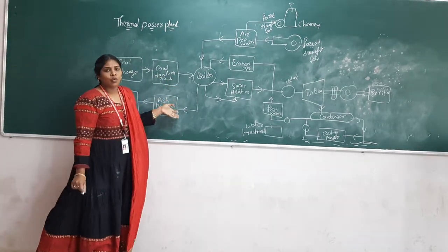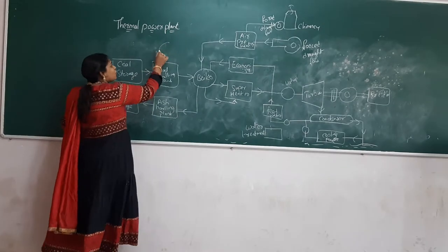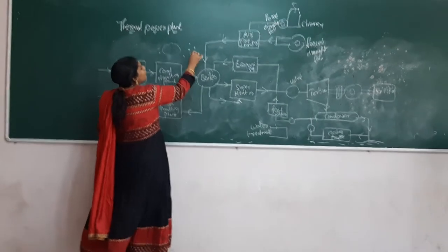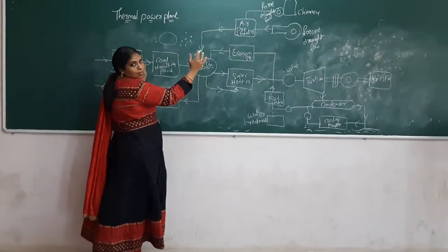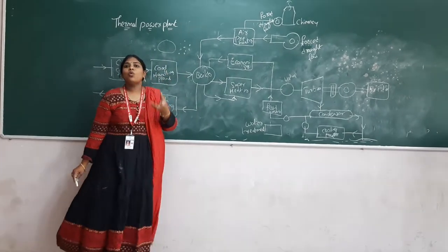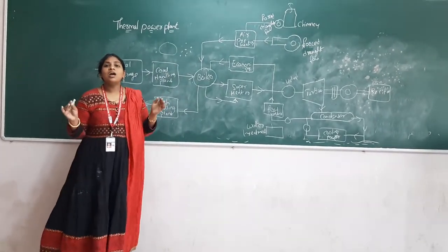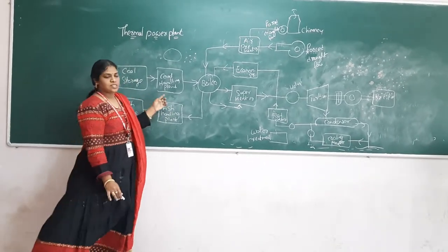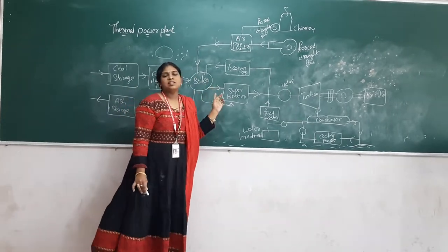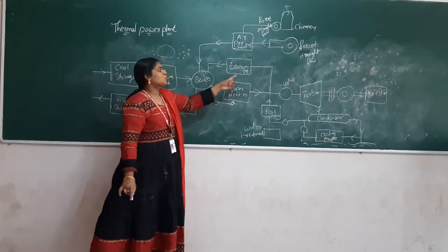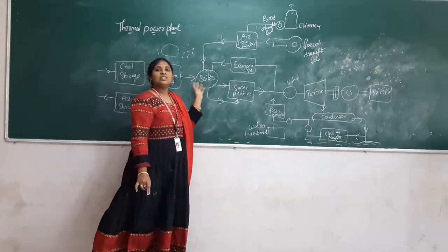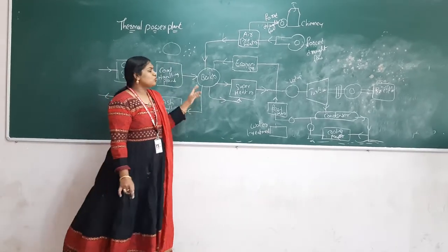The finer the particle, the more surface area is exposed. If you see a big piece of coal versus small pieces, the small pieces have more total surface area, which means we can produce more heat. That is the reason we are pulverizing the coal from big particles into small minor particles. These coal particles are then pumped into your boiler. In the boiler, the coal undergoes combustion and a very high degree of temperature is produced.